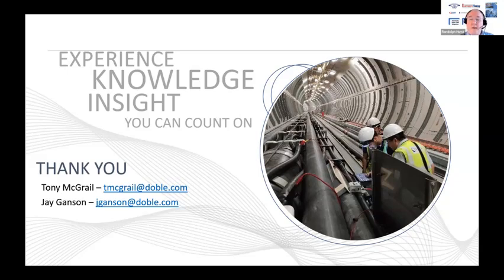We got another question here. Are utilities finding it easy or challenging to justify installing continuous monitoring of cables to regulators? I think it's becoming more common, and when you look at the cost of the monitoring system versus the cost of putting the cable in place, it's a very small percentage. To the question earlier to Chris on whether we should monitor new assets versus old assets, a lot of this monitoring requires an upfront investment and making sure that communication conduits and power conduits are run in parallel with these transmission circuits. So I think that the appetite is there.